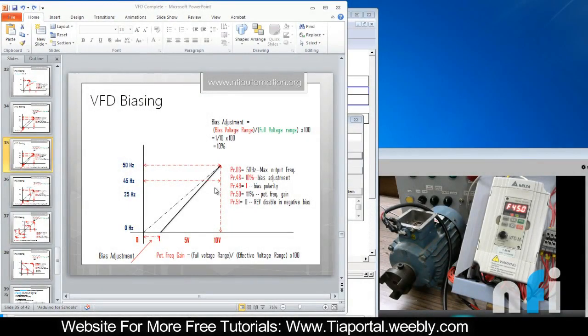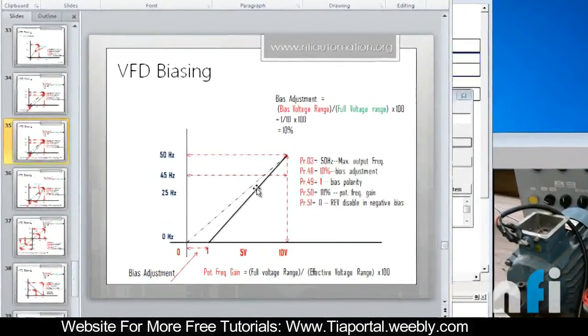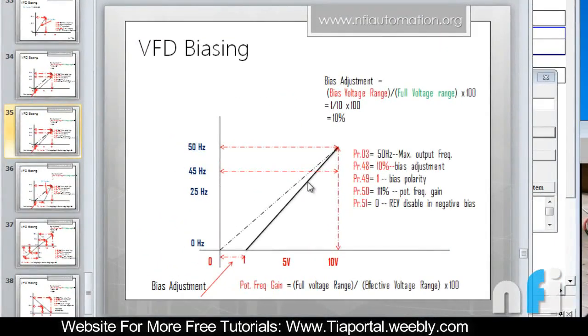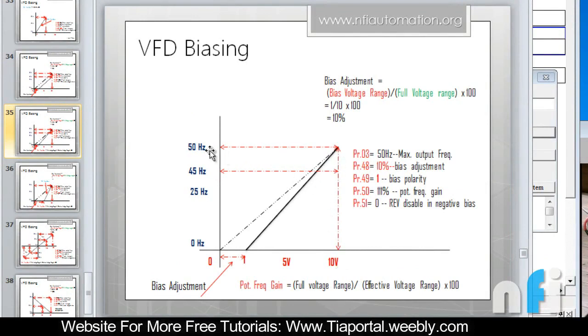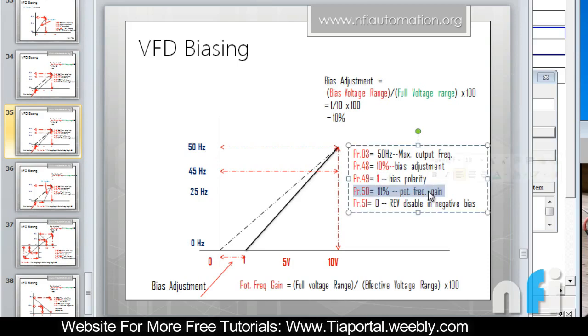In this video we'll see how we can adjust this one. So now this curve is like that - at 10 volt you have to get 50 hertz. In that case, the only thing which we need to change is potentiometer frequency gain.